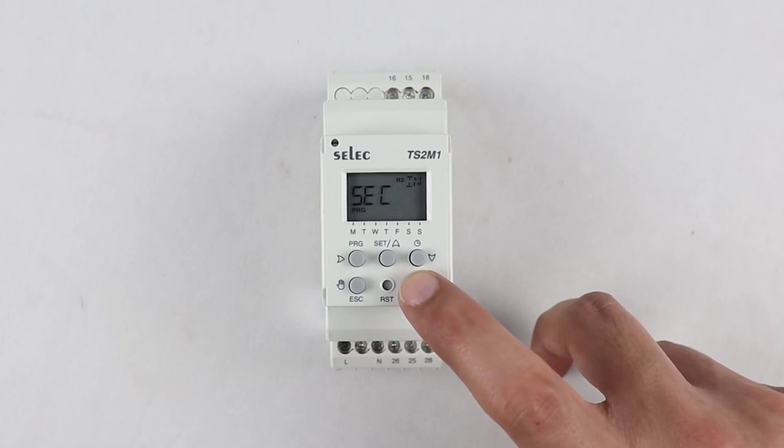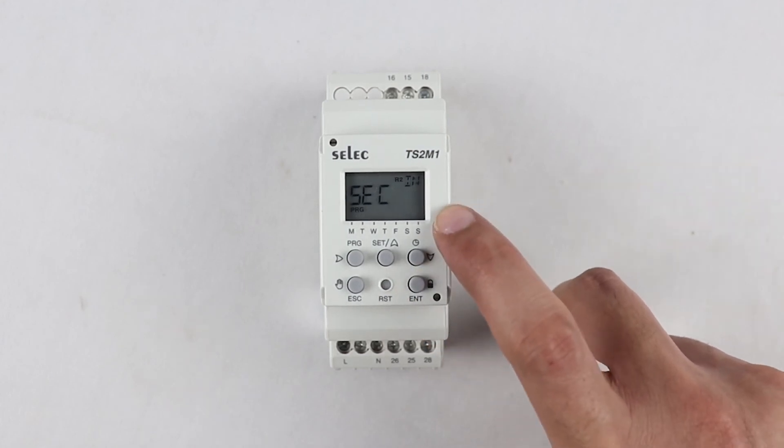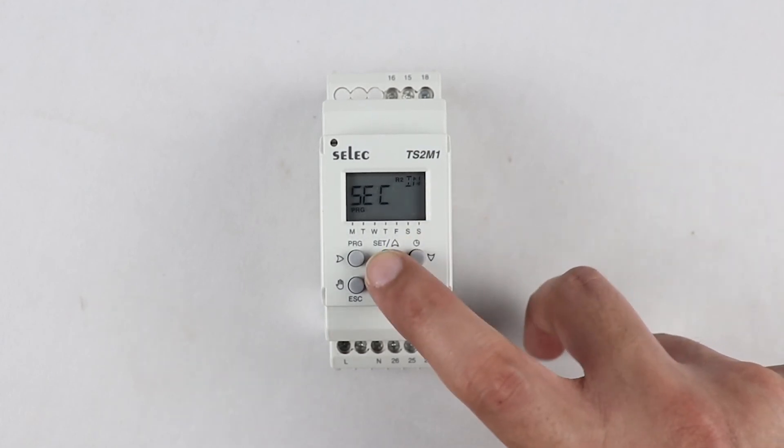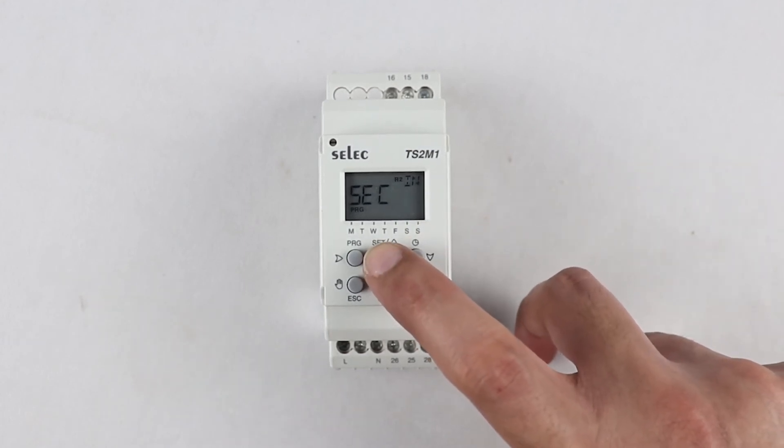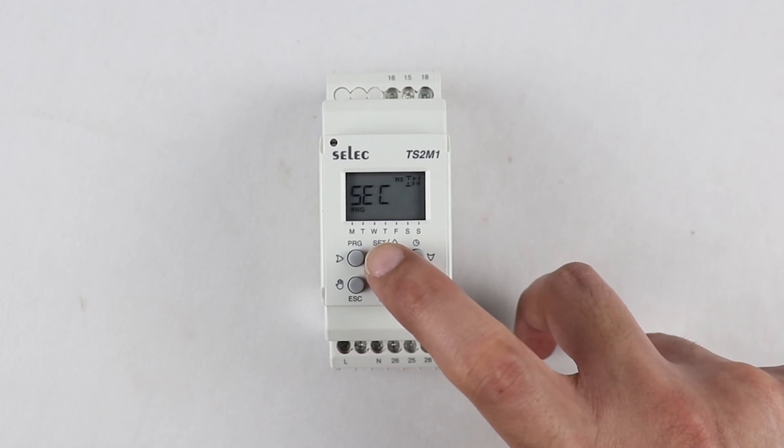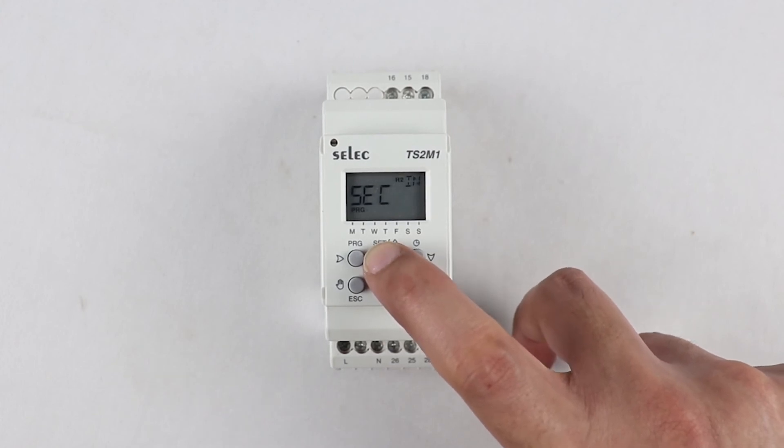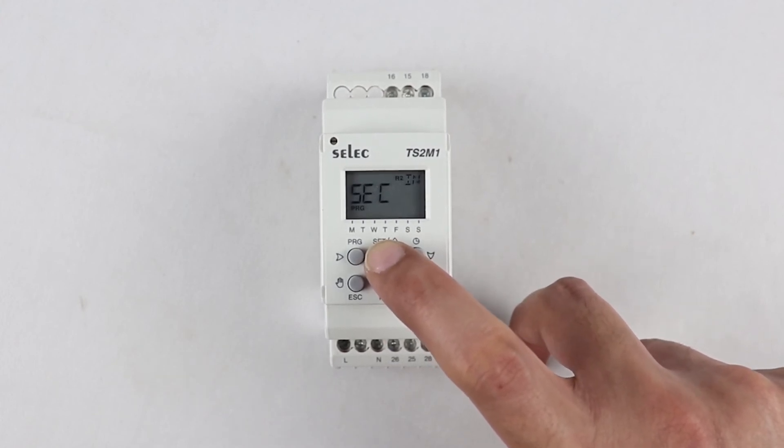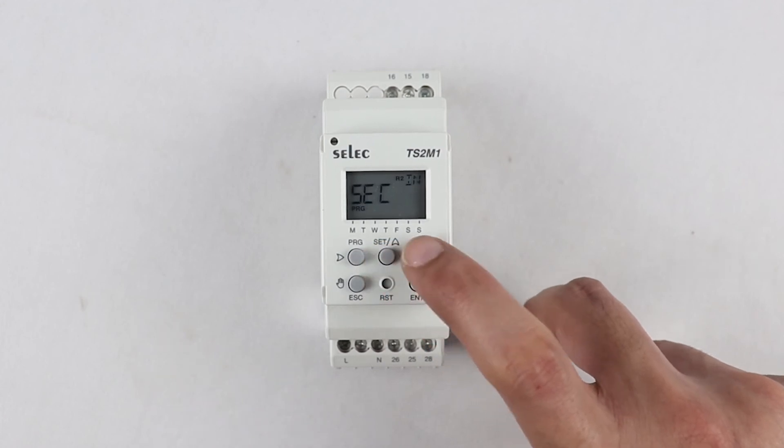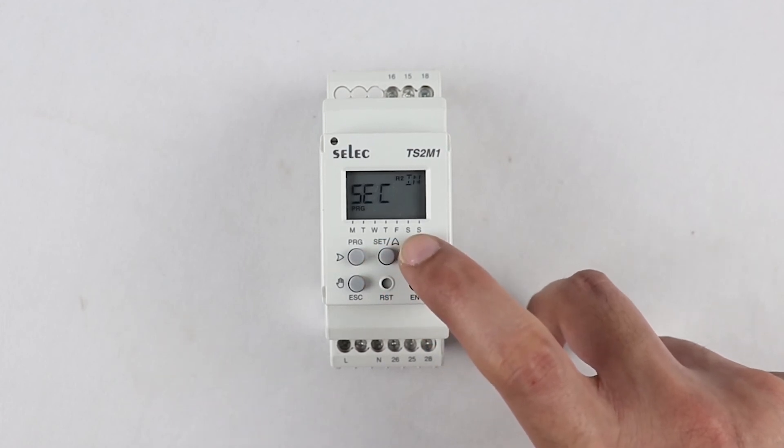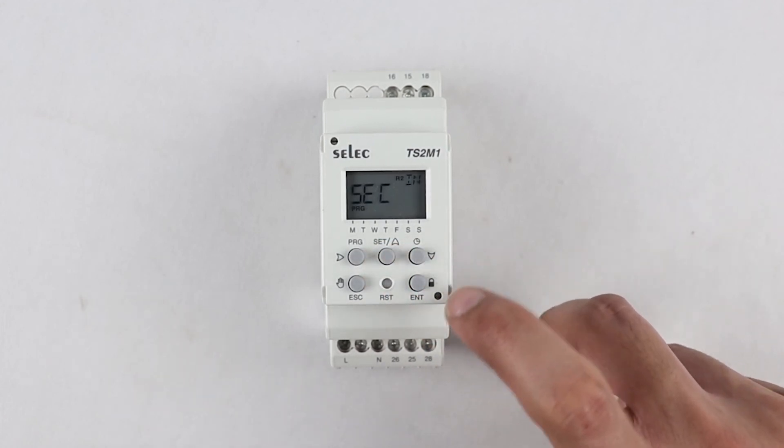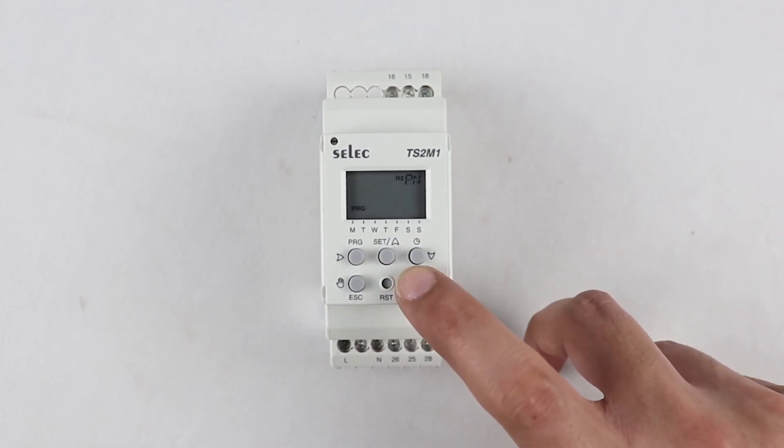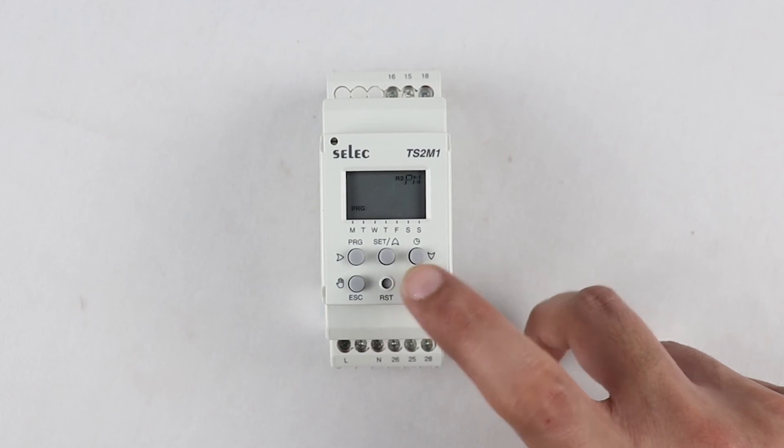Press enter key after selecting pulse mode and increment or decrement the set time using up or down arrow key. The total settable range is 0 to 59 seconds, press enter key to proceed to the next parameter.